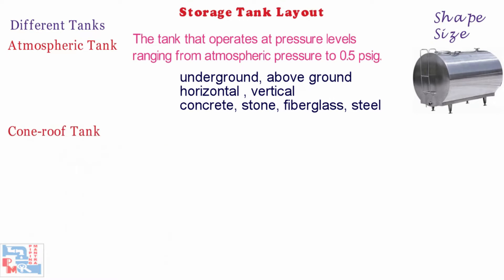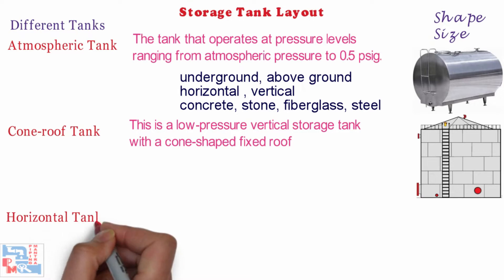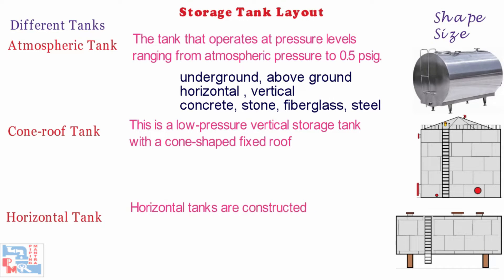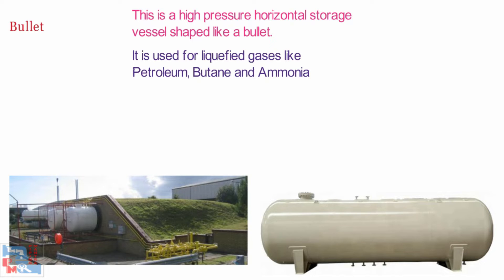Next is the Cone Roof Tank — this is a low-pressure vertical storage tank with a cone-shaped fixed roof. Then comes Horizontal Tanks, which are constructed such that the length of the tank is not greater than 6 times the diameter to ensure structural stability and integrity. Next is the Bullet — a high-pressure horizontal storage vessel shaped like a bullet, usually preferred to store liquefied gases like petroleum, butane, and ammonia, for which the boiling point is low.